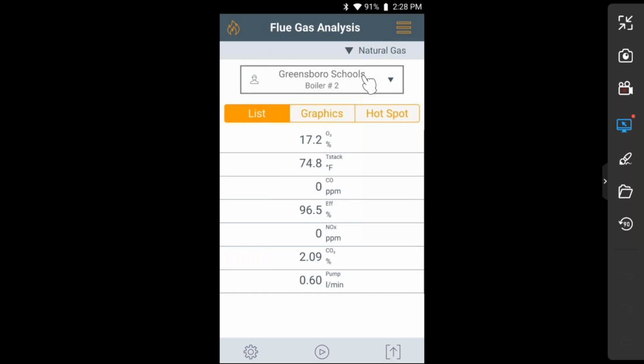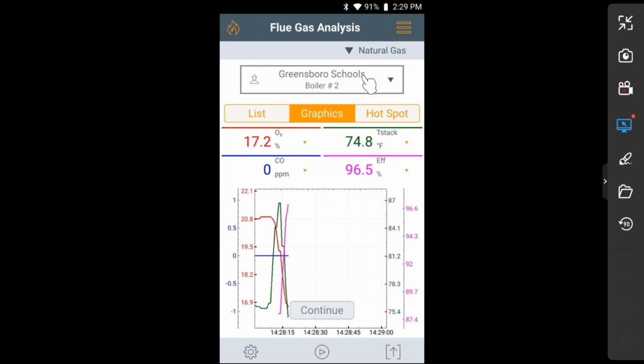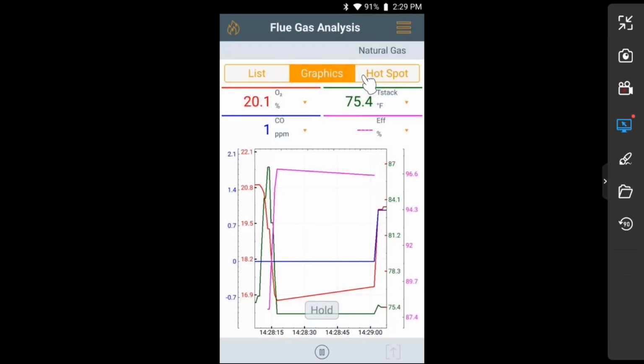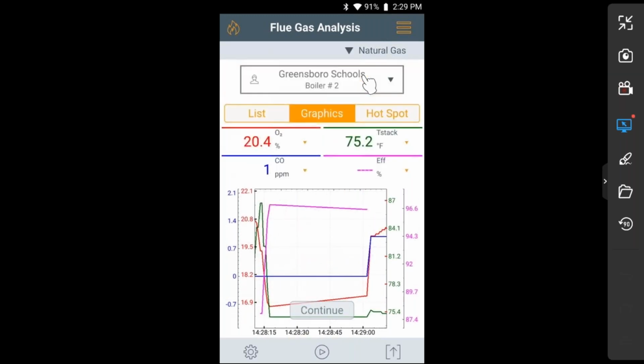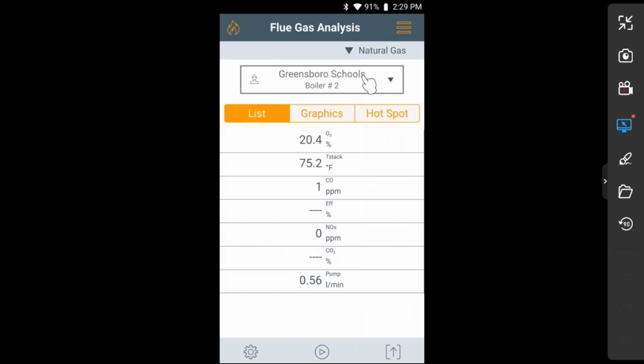You want a trace of carbon monoxide. There's your ppm CO, your calculated combustion efficiency. If you have an NO sensor, that would be your NOx reading, carbon dioxide reading, pump reading. You can also look at this on a graph. So as I turn the instrument back on, you'll see that the lines are changing as everything's coming back up to ambient air conditions. Go back to the list here, and you'll see you can look at these readings on a graphic display, or you can look at them from a number standpoint.